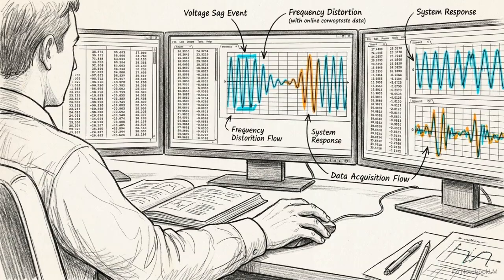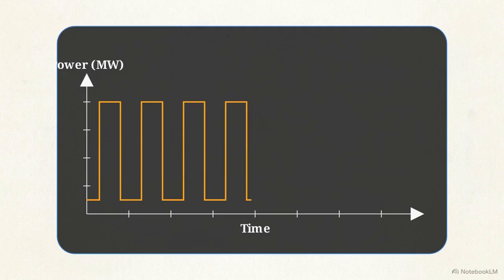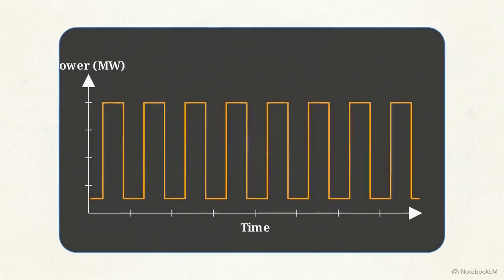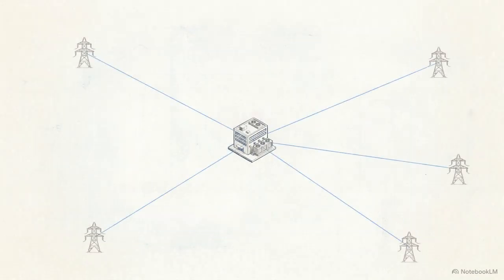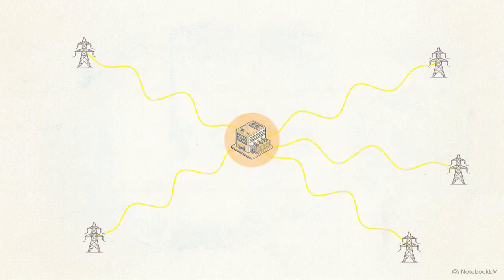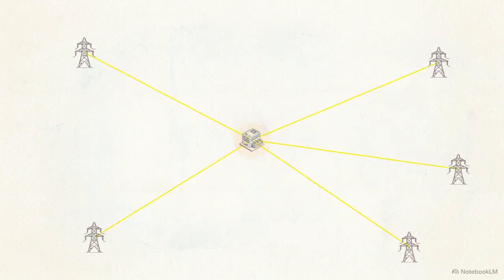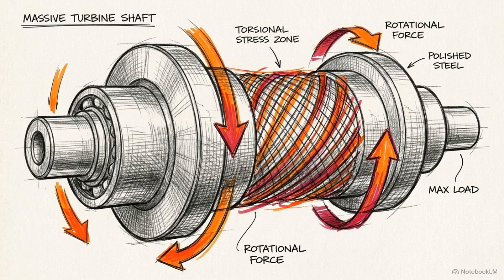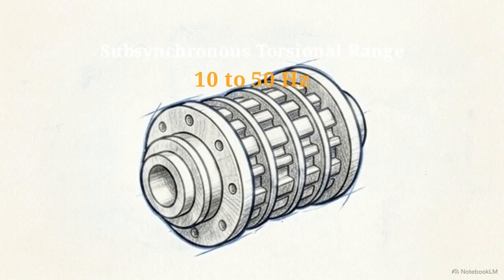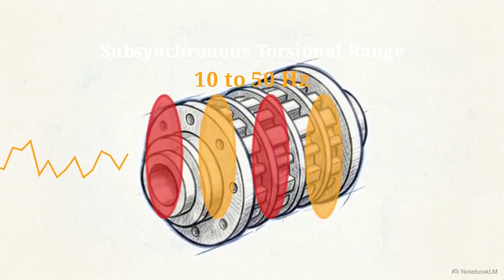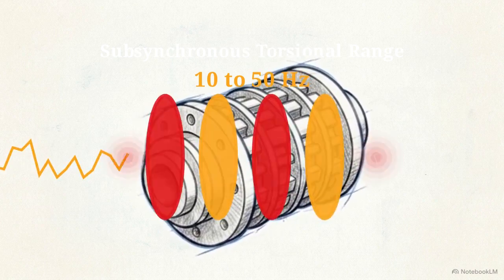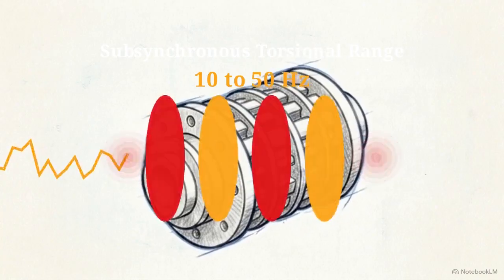Engineers use EMT to hunt specific failure mechanisms, starting with oscillatory interaction caused by the aggressive power ramps of AI training cycles. When a data center load fluctuates rapidly, it can excite the natural oscillatory modes of the grid, creating severe torsional stresses in the physical shafts of nearby steam and gas turbine generators. This diagram shows the physical impact of those oscillations. If the power demand fluctuates between 10 and 50 Hz, it hits the subsynchronous torsional frequency range, physically wearing down the rotating hardware of the generator.